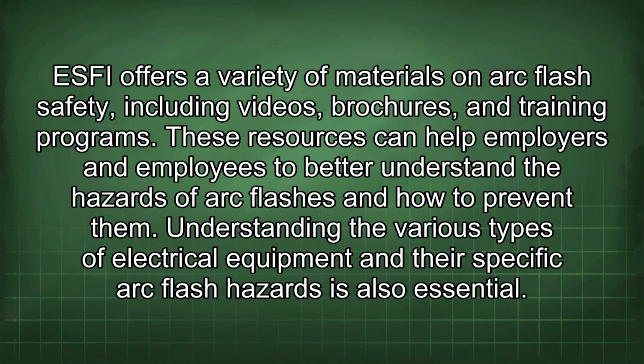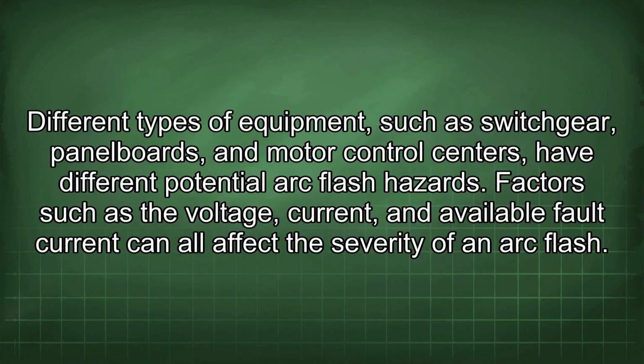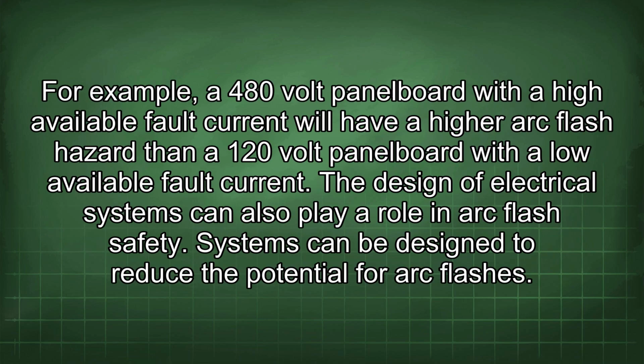Understanding the various types of electrical equipment and their specific arc flash hazards is also essential. Different types of equipment, such as switchgear, panel boards, and motor control centers, have different potential arc flash hazards. Factors such as the voltage, current, and available fault current can all affect the severity of an arc flash. For example, a 480-volt panel board with a high available fault current will have a higher arc flash hazard than a 120-volt panel board with a low available fault current.